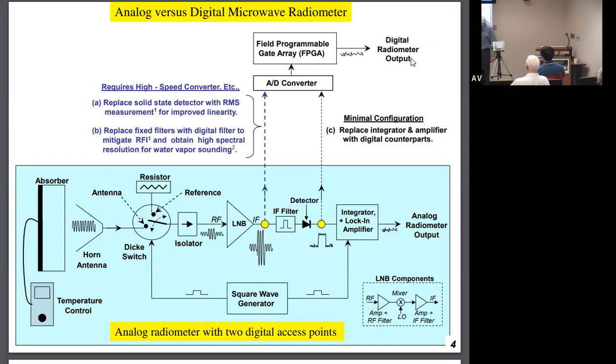So by flipping back and forth and synchronizing the switch that switches this to the switch that switches the output, you can eliminate most of the noise. And you couldn't build a radiometer without it. The other form of radiometer is called the total power, which doesn't have this, okay? And the problem with a total power is you have to calibrate very, very quickly. And that can be done in space because we always calibrate like every second, every couple of seconds. So you can do it, but you can't do it with a ground-based one.